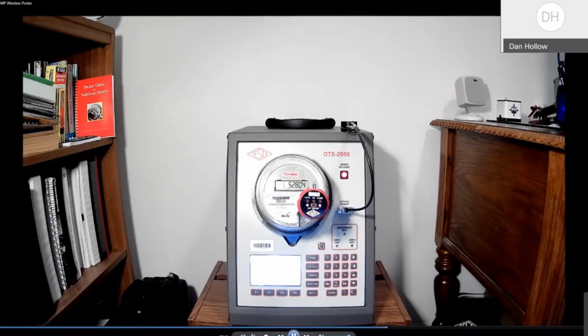And as you can see, the LEDs are blinking now. You see those transmit and receive LEDs flashing back and forth, toggling back and forth between transmit and receive. That tells me there's full two-way communications taking place right now. So now I've connected to the meter. So this is just the log on process I did. After it logs on and can see the meter, then I can have it do various operations. I'm going to do a toolbox because that's a reasonable amount of data that it pulls back.